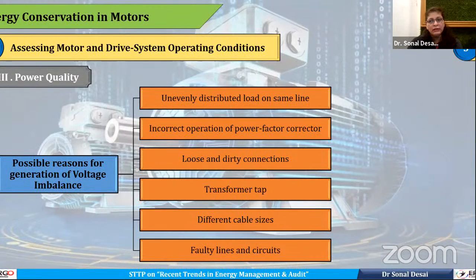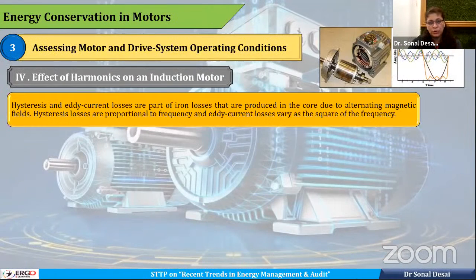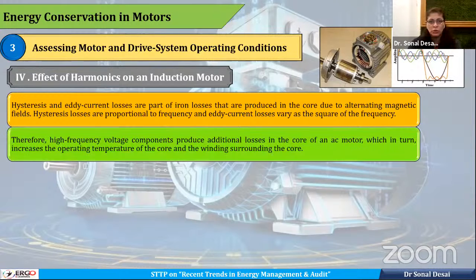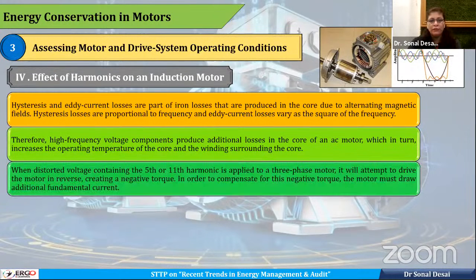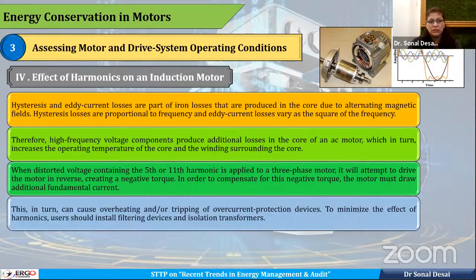Just like power quality, there is an effect of harmonics, which are spikes in the voltage, on the motor. And distorted 5th and 11th harmonics affect the motor performance and need to be taken care of.